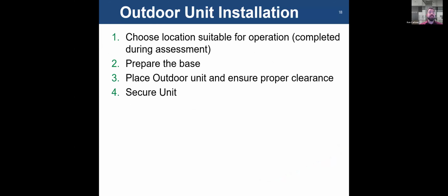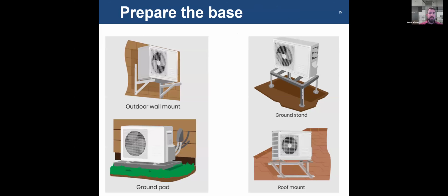So, outdoor unit installation. All right, you've chosen your suitable location during your assessment. You prepare the base, if it's going on the ground. If you're in a cold climate with a lot of snow, chances are your base is not going on the ground. It's going up on a stand or up along the wall. Make sure your clearances are right too. Make sure your unit is secured onto whatever you're putting it on. Different types of bases: ground stands, wall mounts, ground pads, and roof mounts. Roof mounts are probably the least favorable for anybody, but sometimes you have no choice.